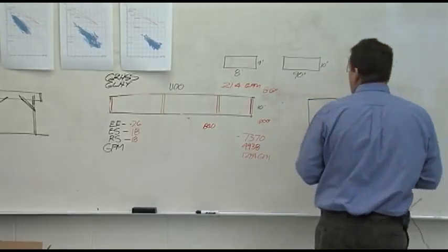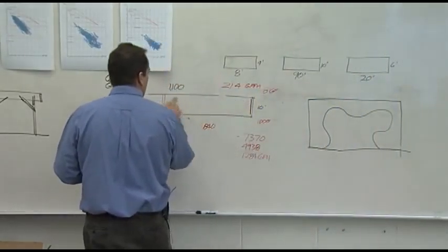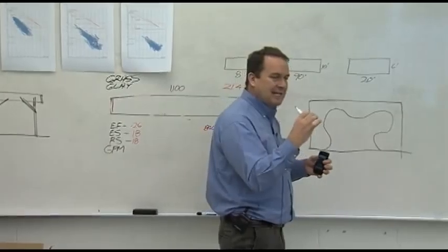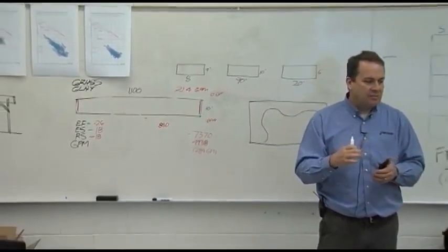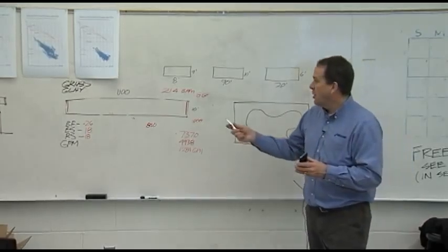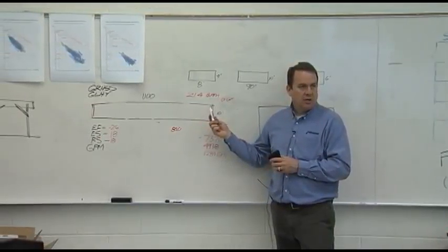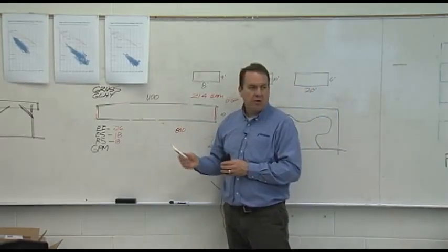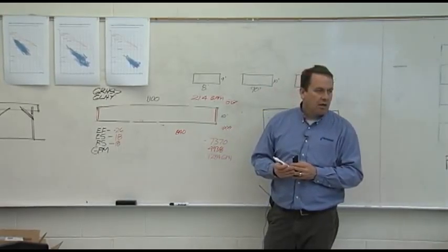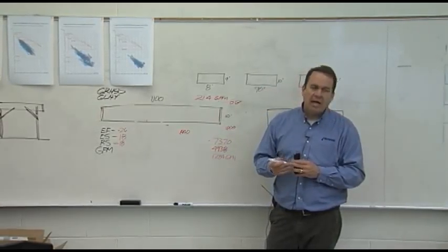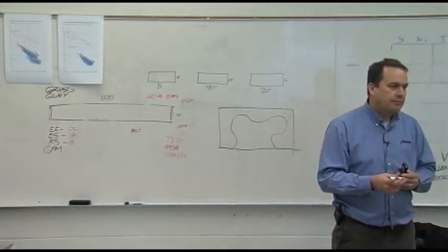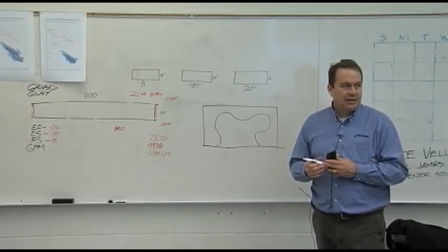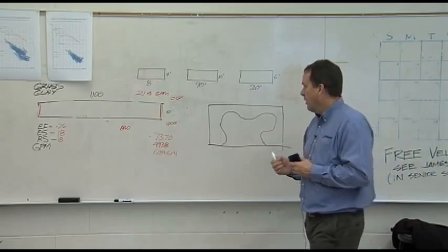No, I missed it. So if we know that our total flow for this whole area is 21 gallons a minute, but our connection is only 8 gallons a minute, that's all that we can get out of it. So we know that we need to divide this into 3 zones. So I'm just going to divide it equally by 3 and create my headers that way. Does that make sense? So where'd you get the 8 gallons? I just made it up. Oh, okay. 8 gallons a minute is a pretty typical residential type of thing, so it's a number out there. Okay. Good job.